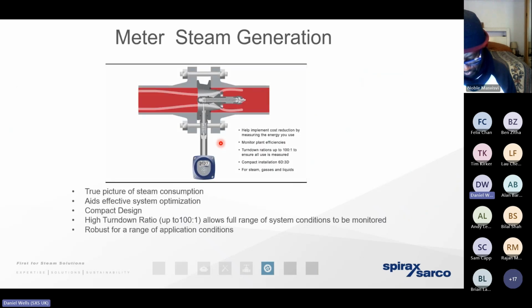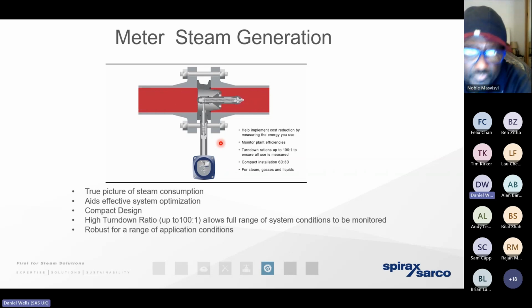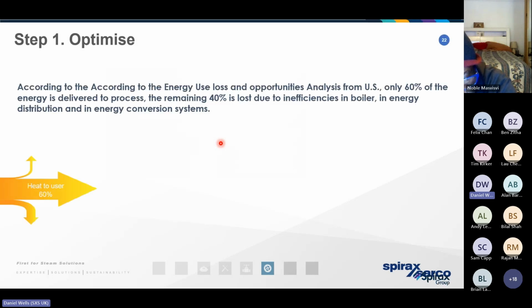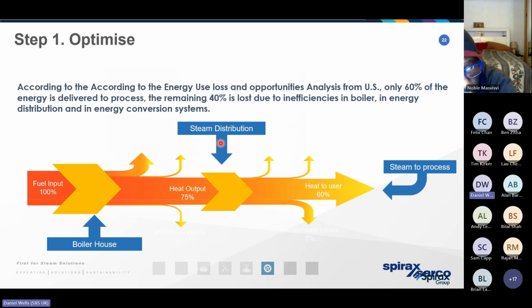So even before we take that leap to look at how and where we can optimize the existing steam system, it's important to ensure that we've got a good number of well-designed meters on each steam boiler. By understanding the mass of steam that's produced, that will help us understand our cost of steam. And when we understand how much steam each individual process or heat exchanger is consuming, we can then get a better understanding for where the inefficiencies exist between the point of generation and the point of use. Without steam meters, we simply don't have that data or that information available. So with a traditional steam system, we know where those inefficiencies are likely to be.